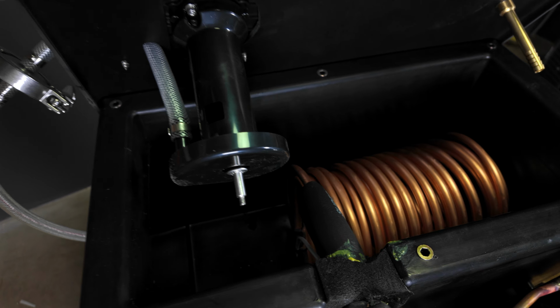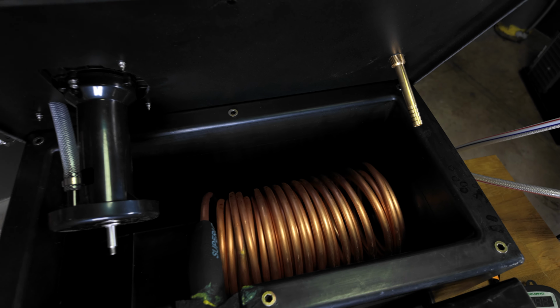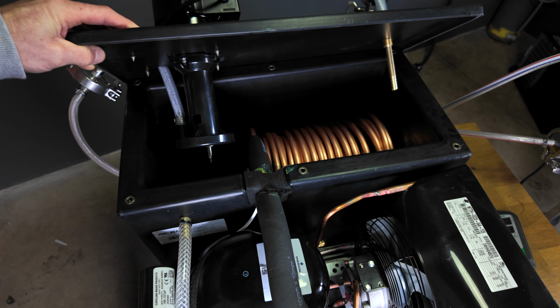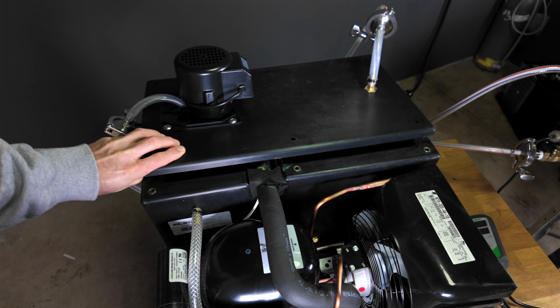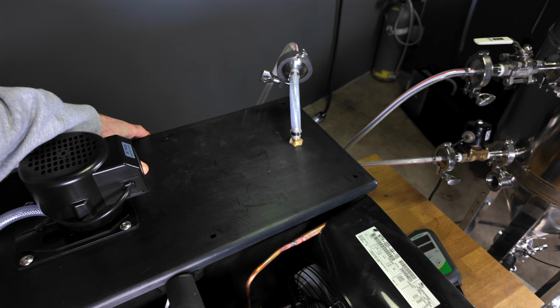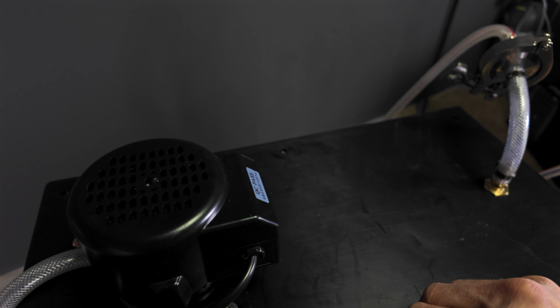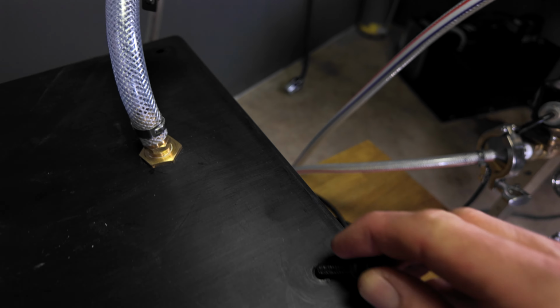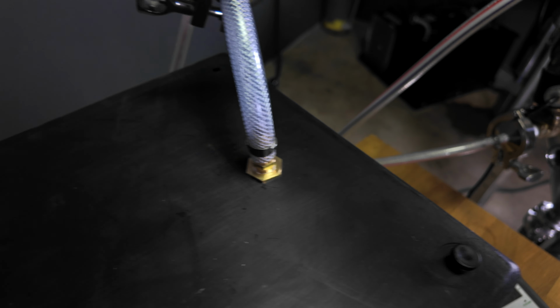Once you have your Glycol, you'll want to mix it with water before adding it to the reservoir. A typical ratio is about 30 to 40% Glycol and 60 to 70% water. This gives you proper freeze protection, good heat transfer, and keeps the fluid thin enough for the pump to operate efficiently. Start by adding your water to the reservoir, then add the Glycol.